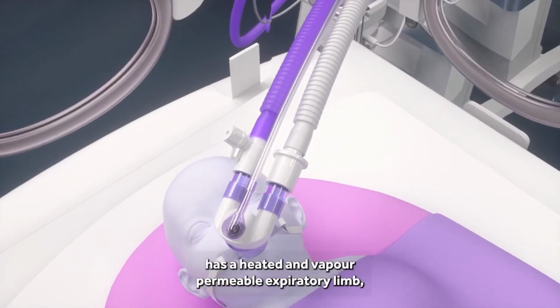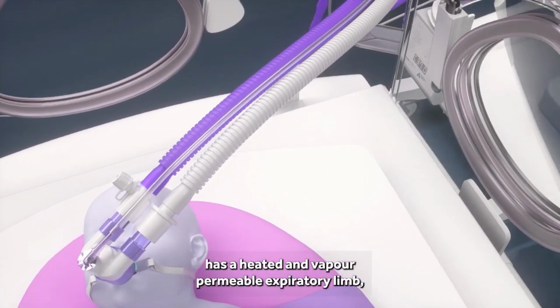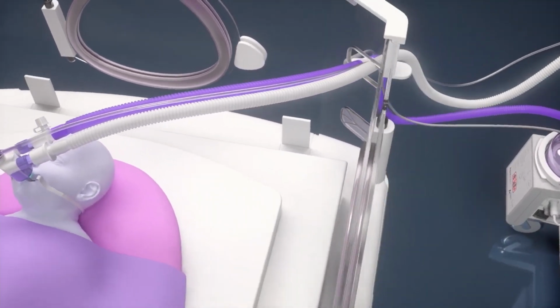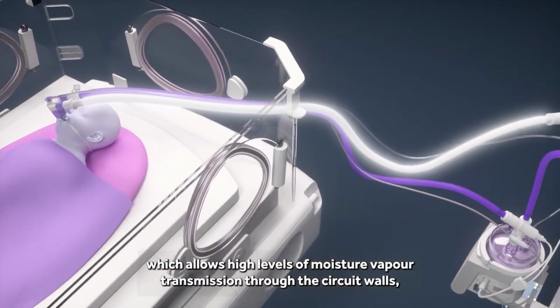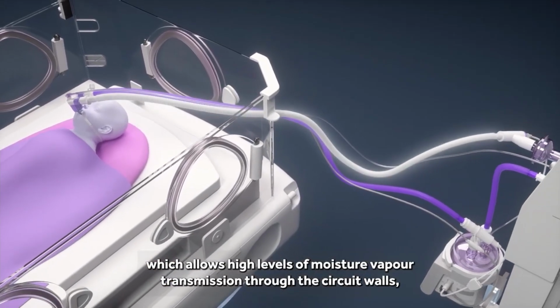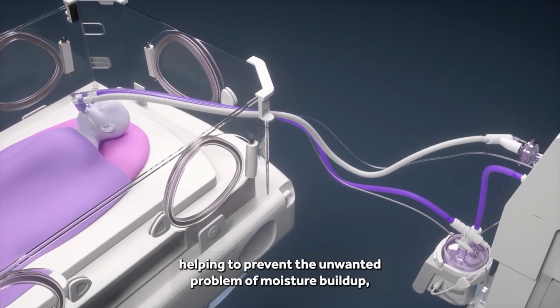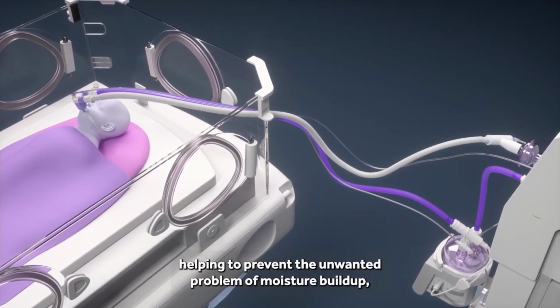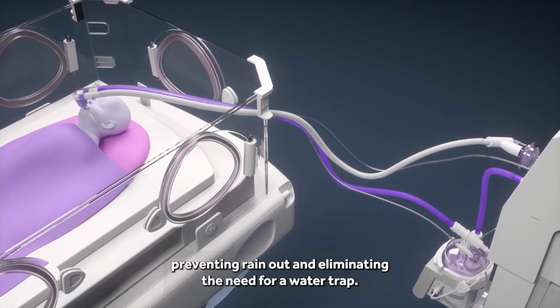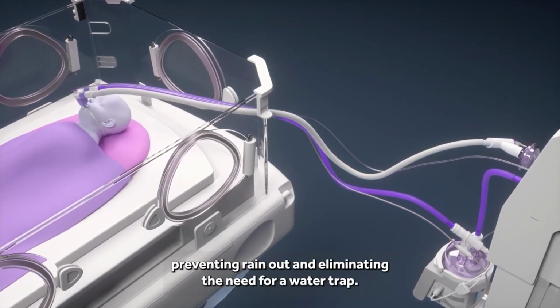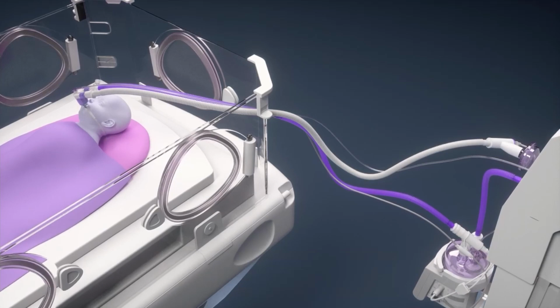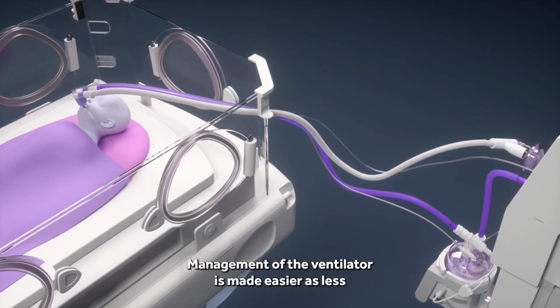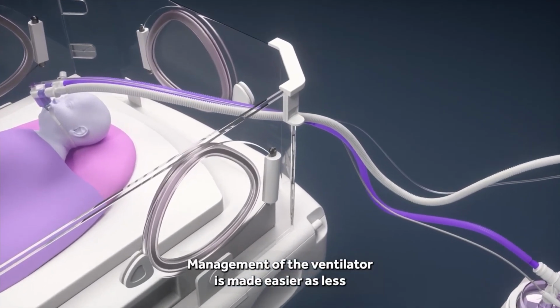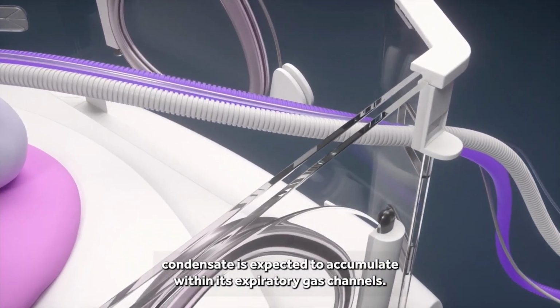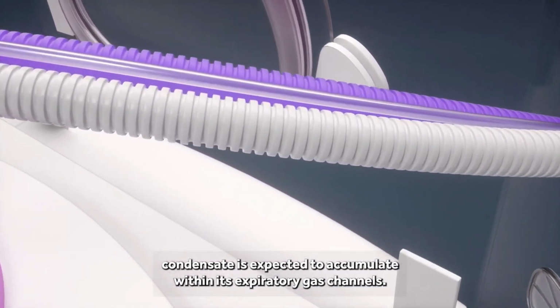NeoFlow VT has a heated and vapor-permeable expiratory limb, which allows high levels of moisture vapor transmission through the circuit walls, helping to prevent the unwanted problem of moisture buildup, preventing rainout and eliminating the need for a water trap. Management of the ventilator is made easier, as less condensate is expected to accumulate within its expiratory gas channels.